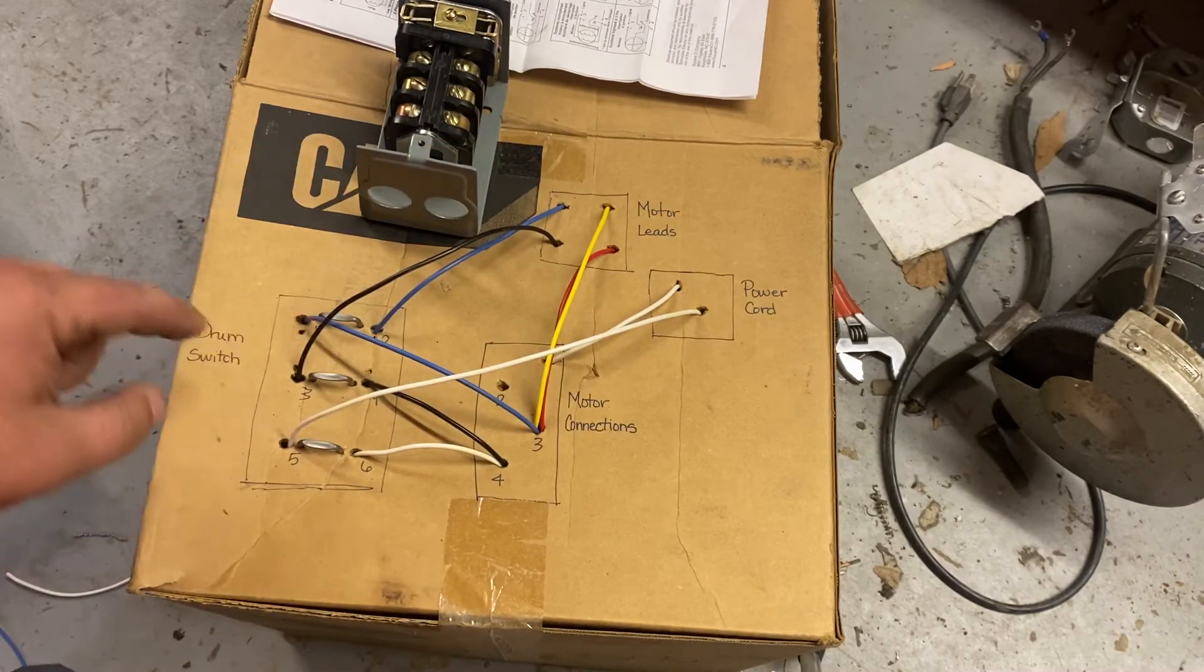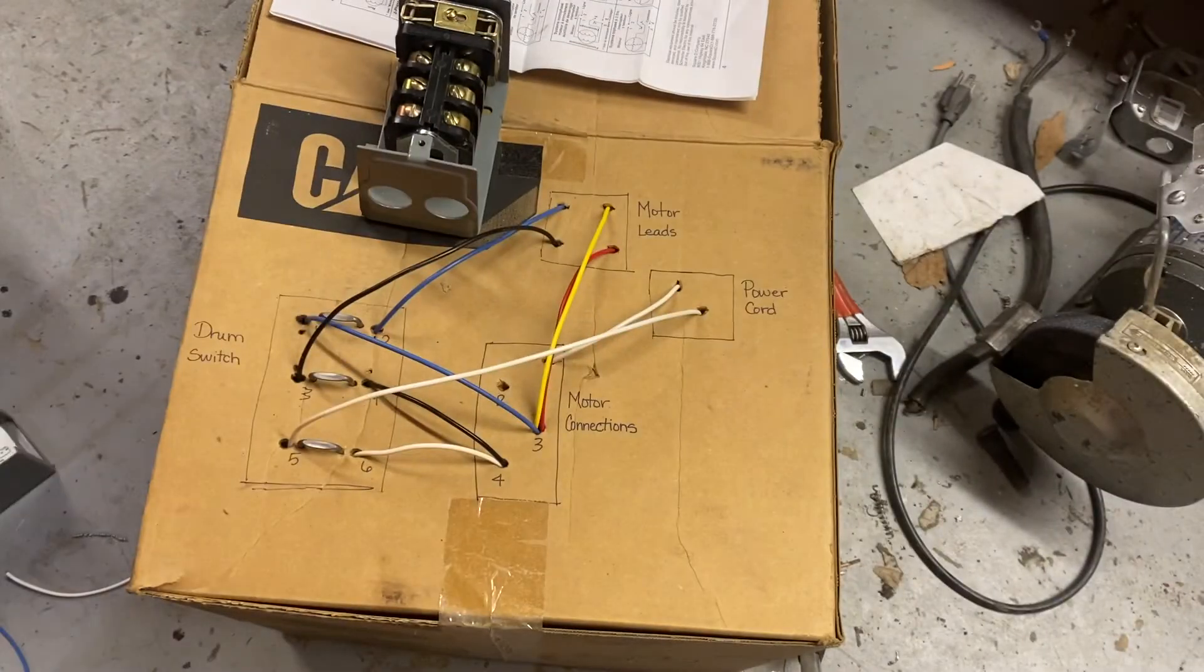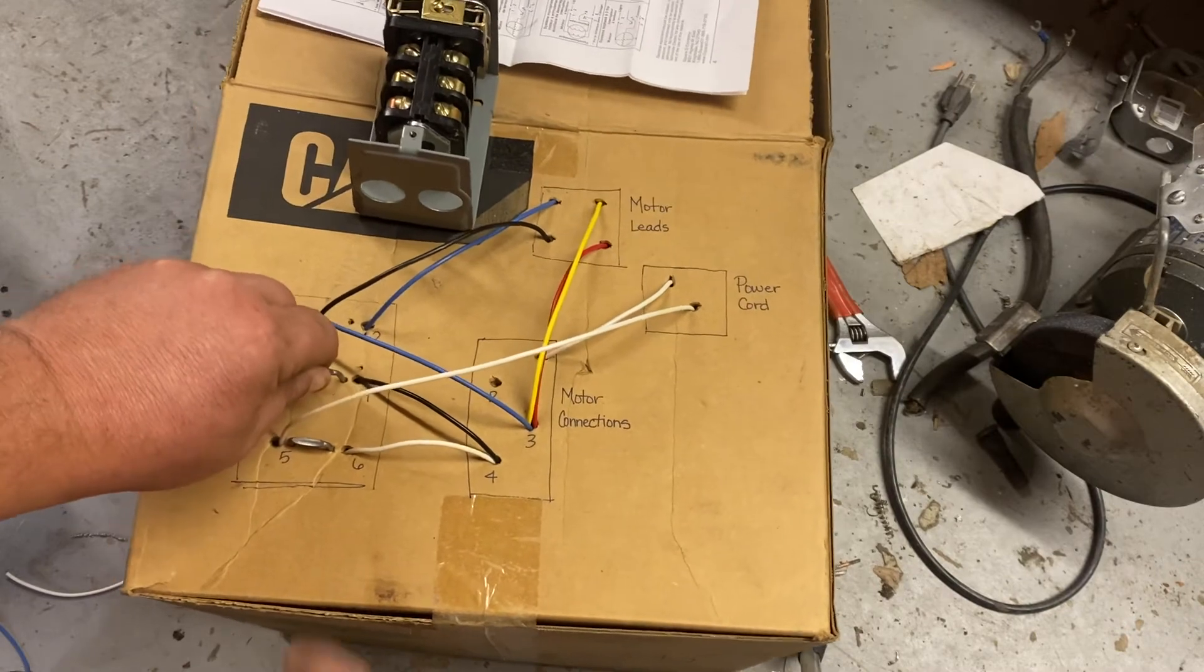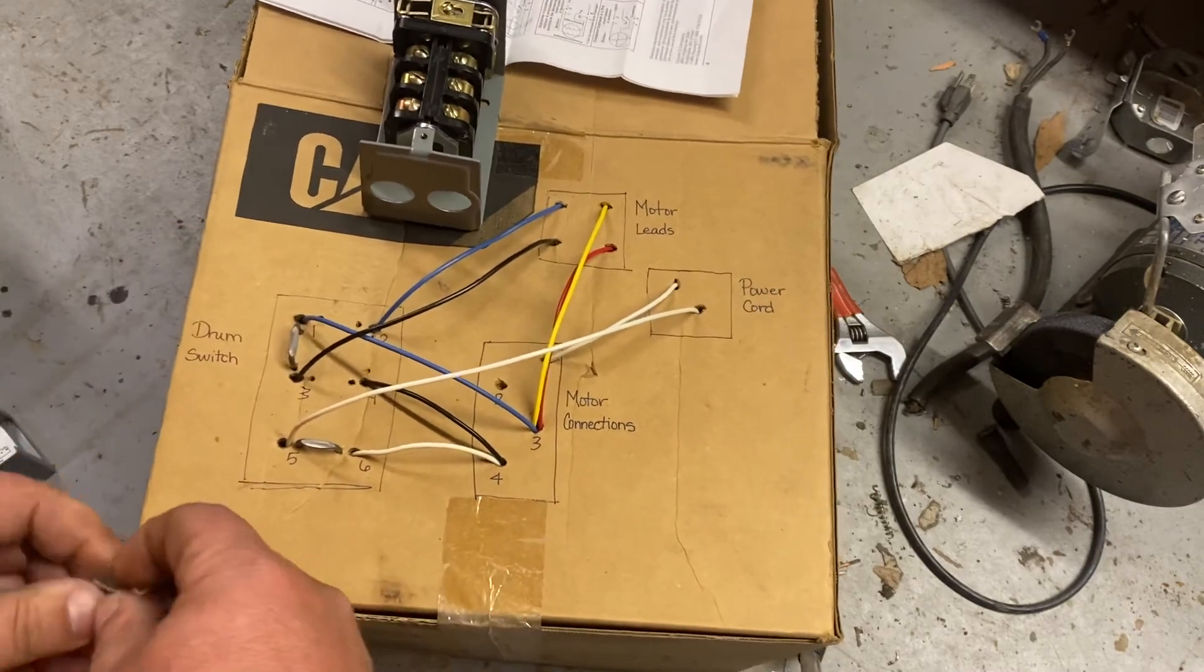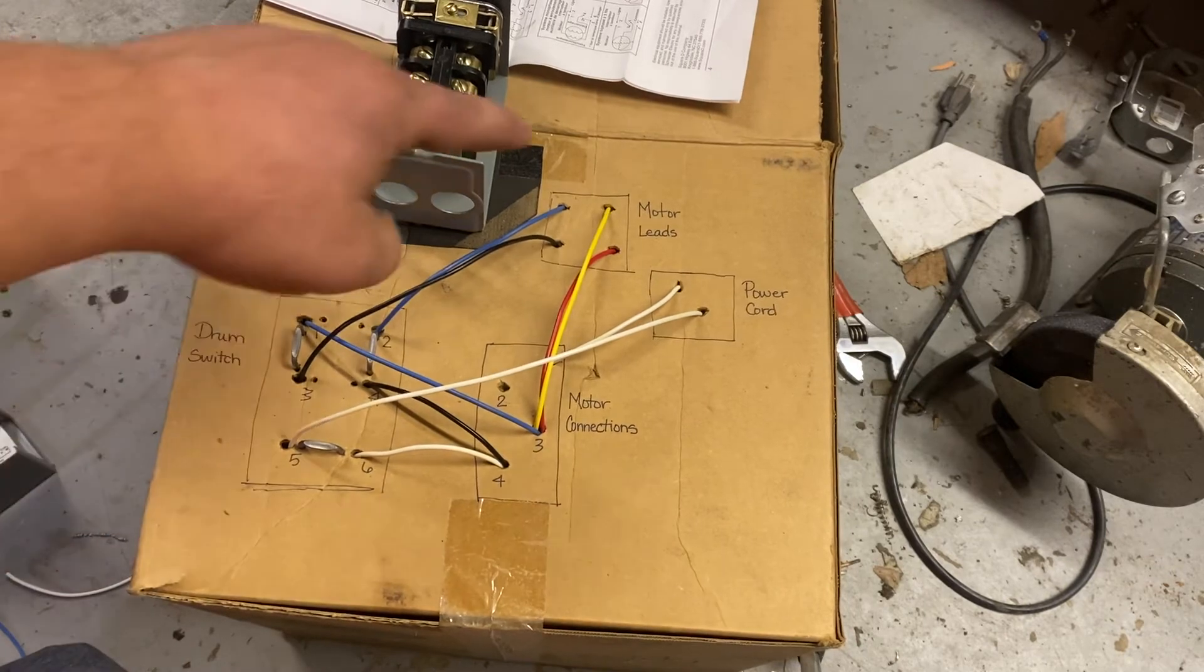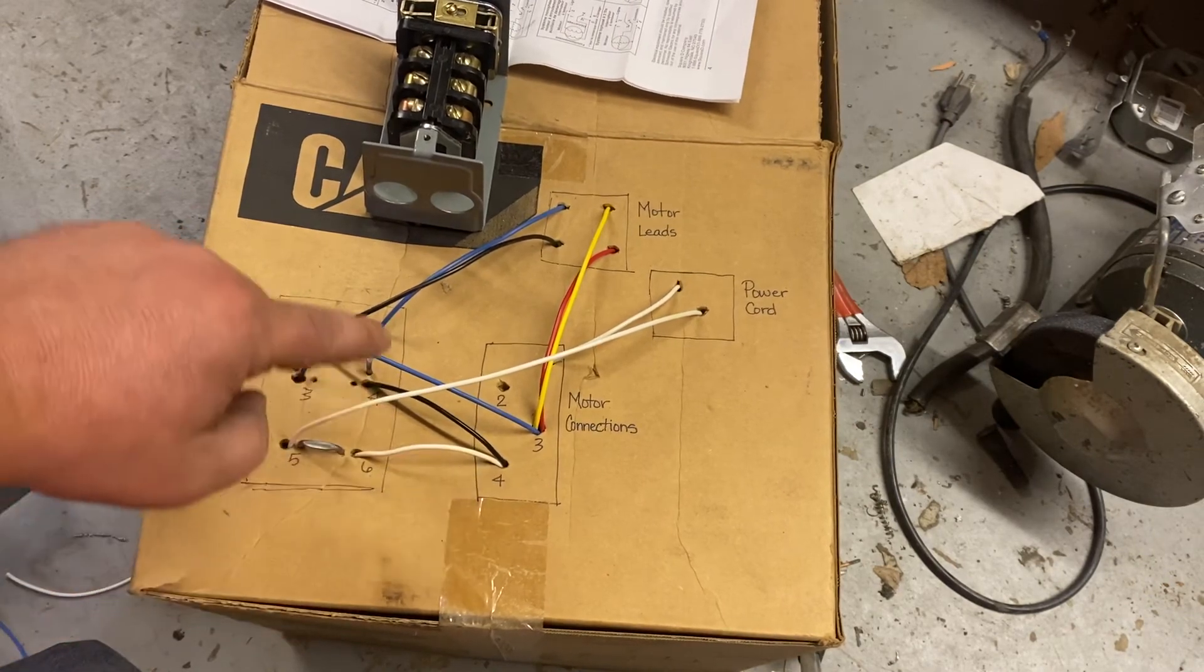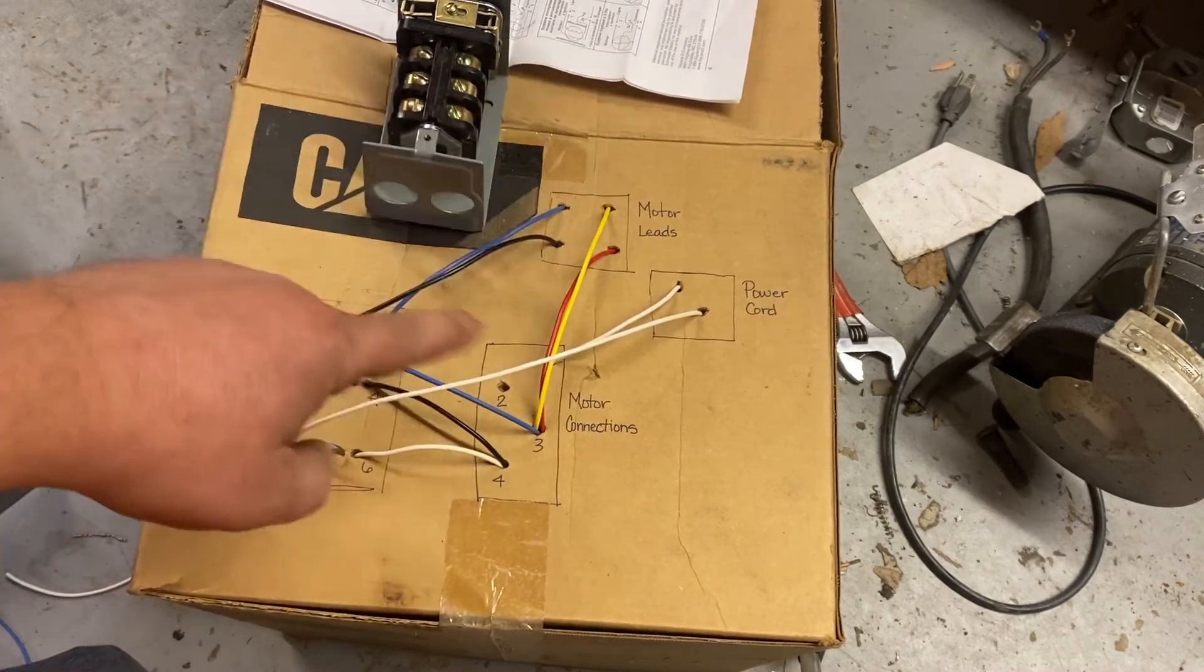Now in this switch, when you flip it to the reverse position, it flip-flops those positions. So now the blue wire is turning into the black wire, so the motor lead has been swapped to position four. And the black wire is going here and is being swapped to the blue lead going to position three. And this will reverse the motor.